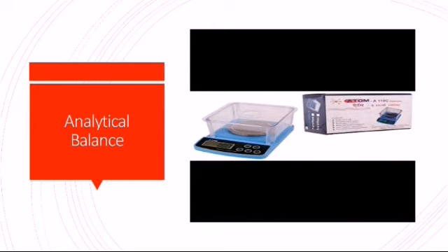The use of a mechanically vented balance safety enclosure, which has uniquely designed acrylic airfoils, allows a smooth turbulence-free airflow that prevents balance fluctuation and the measure of mass down to 1 μg without fluctuations or loss of product. Also, the sample must be at room temperature to prevent natural convection from forming air currents inside the enclosure from causing an error in reading.